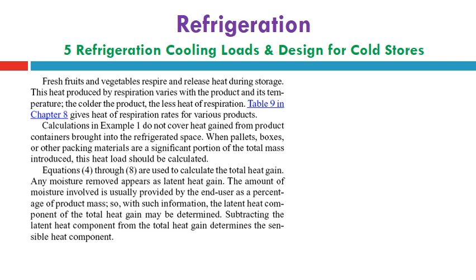Please take note that meat products, fish, chicken, shrimps, and any meat products have no respiration loads. The respiration loads apply only, as mentioned in this slide, to fresh fruits and veggies, not to frozen fruits or veggies. Fresh fruits must be kept above zero, above freezing, to keep them fresh. So we have to consider the respiration load according to the product, its chemical composition, and the outside surface.